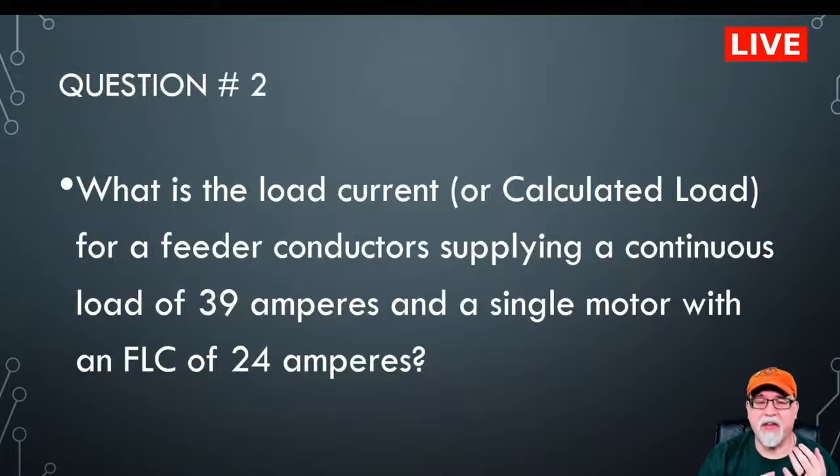Some people will say, well, wait a minute, I need to know the nameplate. No, you don't, not to answer the question. In real life, you might need additional information. Obviously, if you go to overloads, you have to have a nameplate, because overloads don't use the FLC. They use the FLA, or the amps listed on the nameplate. But everything else, short circuit and ground fault protection, conductor sizing, feeders, all of those use the FLC values.